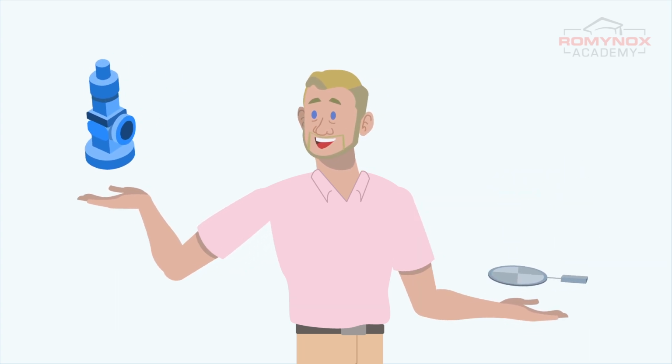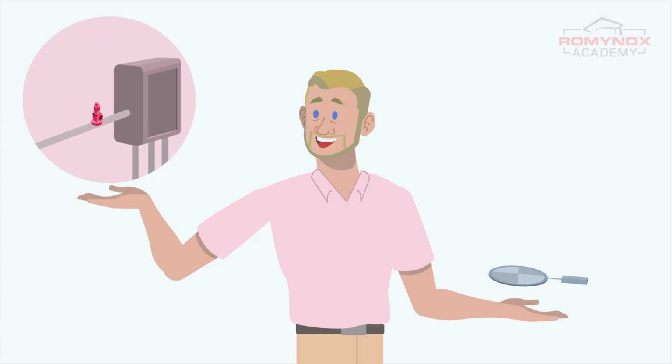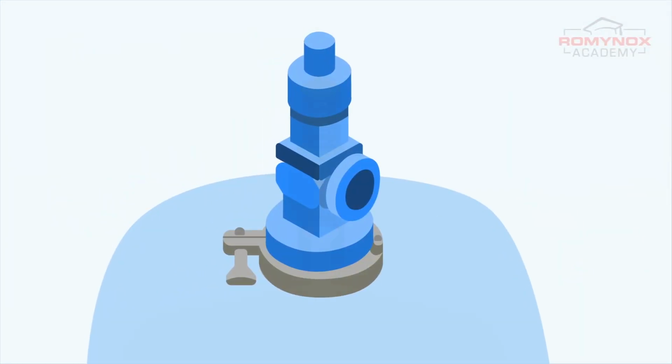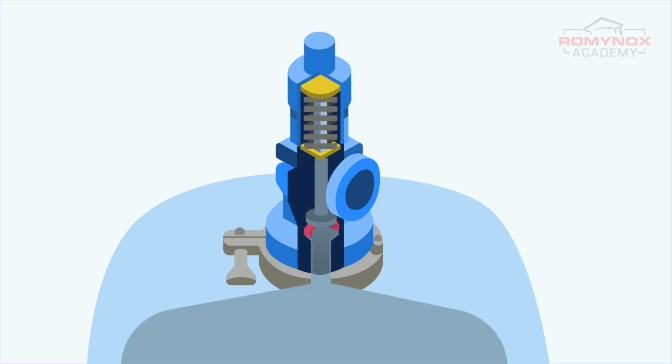A spring-loaded device or safety valve is the most common type of pressure relief. You will even find them in your own home. The operating principle is very simple. A valve is kept closed by a spring and is forced open if a preset pressure level is exceeded. Simple in operation and easy to adjust, a safety valve often is the first option to be considered.